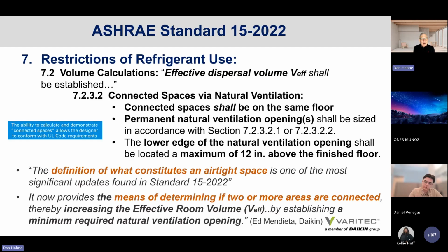Connected spaces, however, if they're going to be used to expand the effective dispersal volume of the occupied space, shall all be on the same floor. They cannot be interconnected through multiple floor levels. Permanent natural ventilation openings shall be sized in accordance with section 7.2.3.2.1 and 2.2. This is an important development.